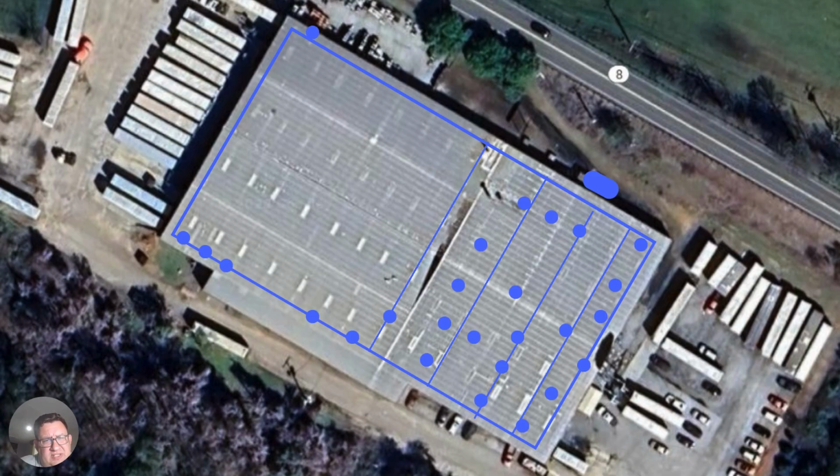Now, we start to see a little bit of benefit here, because if you put isolation valves in on both sides of these crossheaders, you can isolate that and do work on that crossheader. Whereas in the whole loop, shutting an isolation valve doesn't do anything except make a really big single header design.